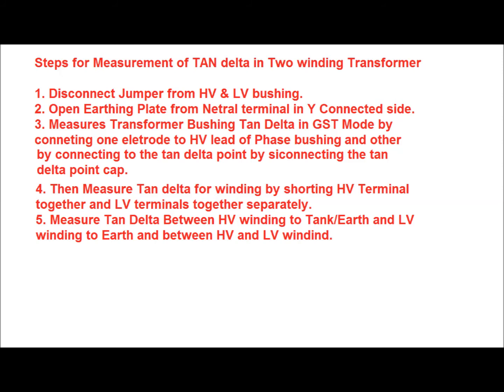Then we have to measure the tan delta for the winding by shorting all the HV terminals together and LV terminals together separately. Then we measure tan delta for the winding: HV to earth, LV to earth, and between HV to LV.